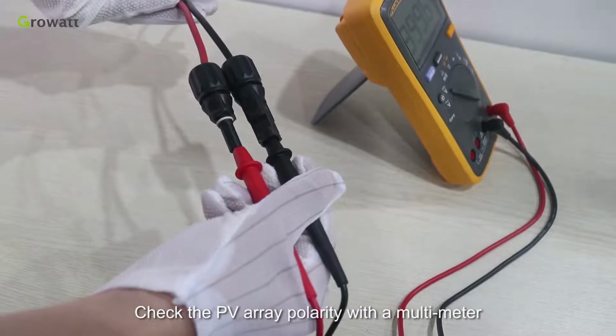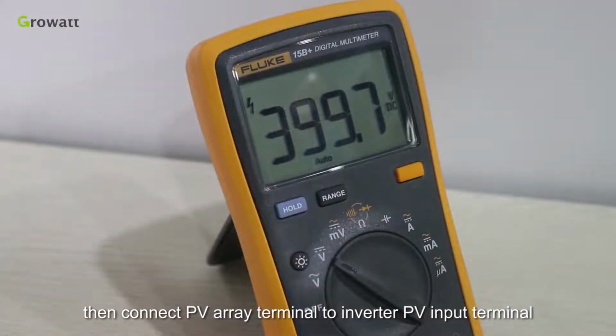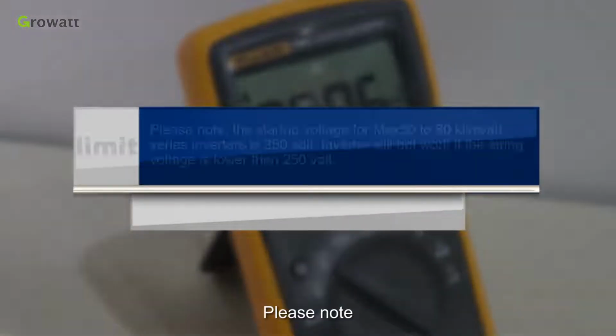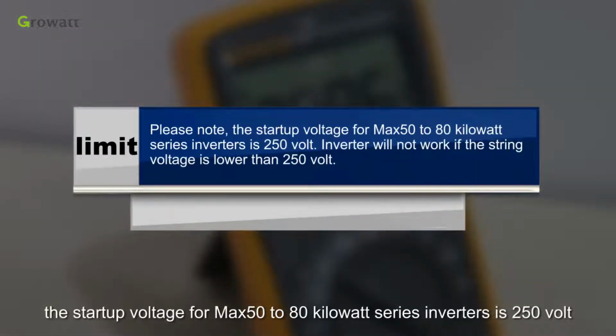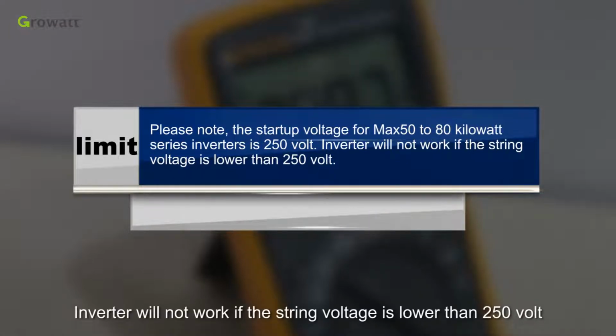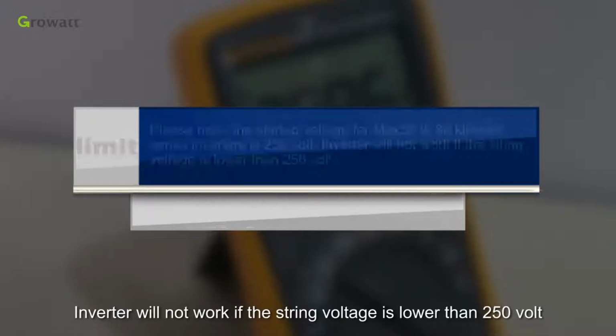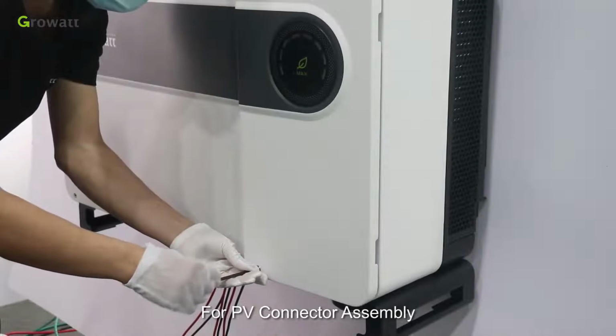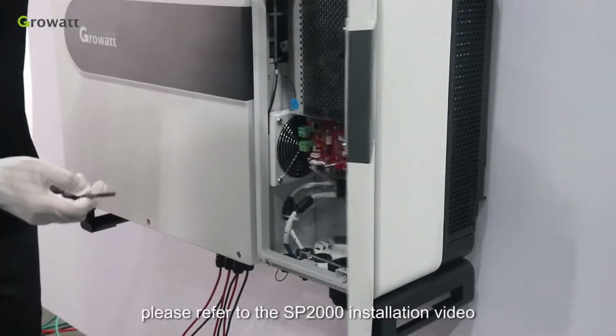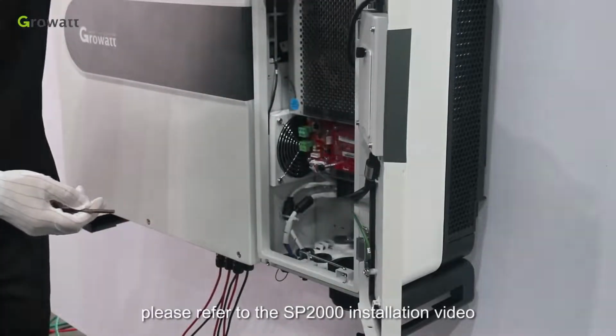Check the PV array polarity with a multimeter. Then connect the PV array terminal to the inverter PV input terminal. Please note, the startup voltage for MAX 50 to 80 kW series inverters is 250 volts. The inverter will not work if the string voltage is lower than 250 volts. For PV connector assembly, please refer to the SP2000 installation video.